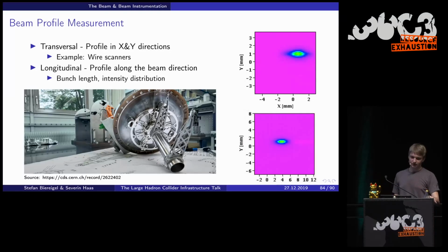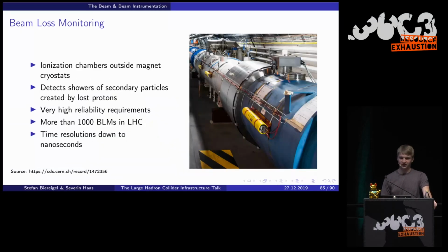And the other one is the longitudinal profile, which gives you an idea about the quality of your RF system. There you want to know what the intensity profile of your beam looks like if you were looking only at one spot of the accelerator and the beam would pass by, and you would basically see over time what the intensity looks like. And then as the last bit of beam instrumentation, there are the beam loss monitors. They are these yellow tubes that are located on the outside of mostly all the magnets, of the dipole and quadrupole magnets and so on.